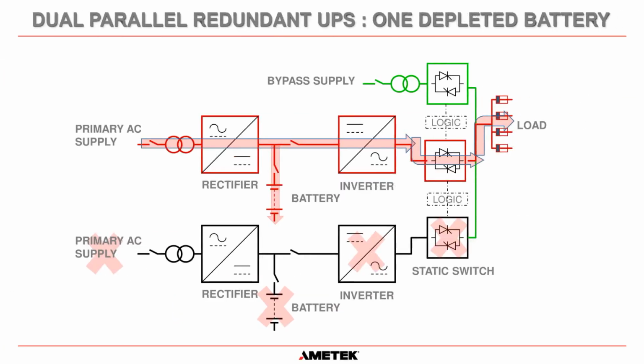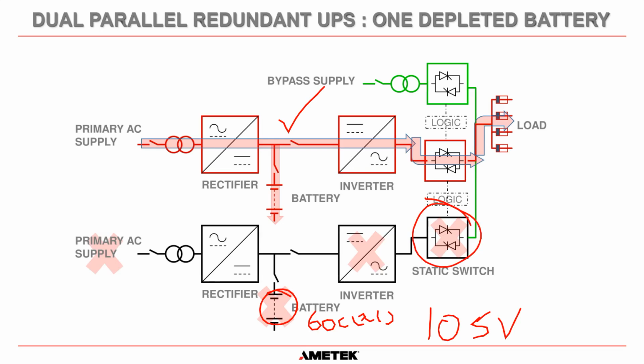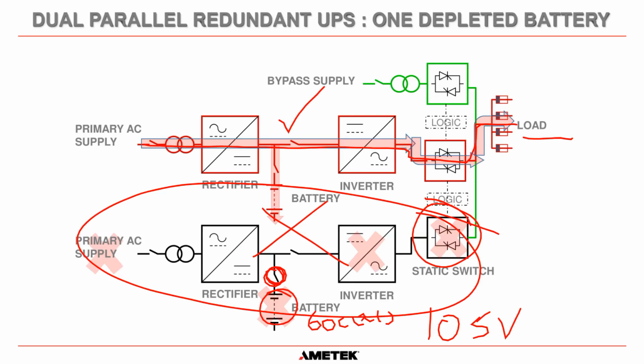And then if we get to a situation where this battery, once again, if it was 60 cells, got down to 105 volts DC, then this system here will, in normal operation, if it was a single system, try to transfer the system to bypass. But because we know that this UPS here is healthy, what it does is it switches this static switch off, and then it trips this battery breaker here to protect the batteries. And this UPS here will continue supplying the power to the load without any issues whatsoever. Your loads will not see anything happening. They will just carry on being fed by the UPS. And basically this system here is now out of action. Okay.